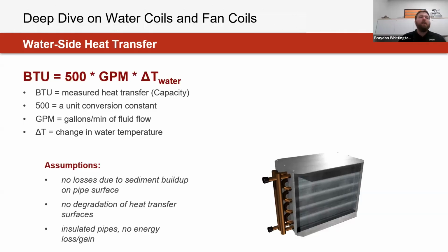But with that, again, there are also other forms of different assumptions that do come into play, in terms of maybe even what insulation is going to be used, in terms of energy transfer for losses or gains of what is actually happening to that coil in the field. And then even for some of those older projects that you might see that are retrofits or older systems, degradation of some of the surfaces of that coil, and what influence does that really have on its overall heat transfer there as well.